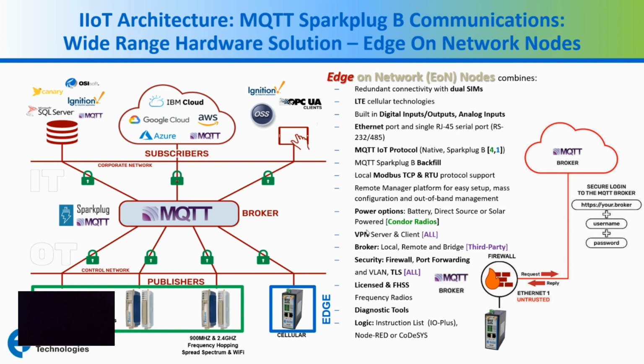But if that ping or the keep alive ever breaks, it will let you know that you have stale data. So, in comparison to Modbus, it's a more inefficient whole network, where it goes out to each one of the nodes, asks for the data 3 times, and then if it doesn't see that data communications, it'll throw a flag and give you an error. It's very inefficient and it does not have any security to encrypt that data.